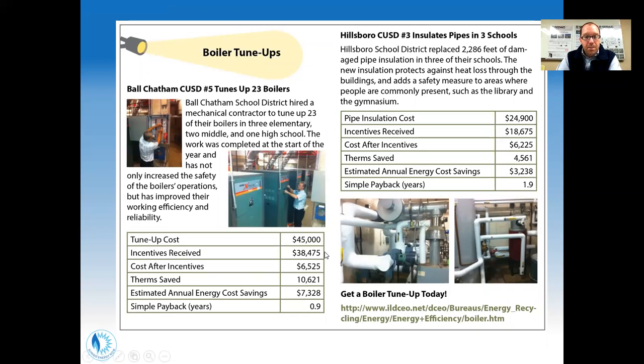The tune-up cost for these 23 boilers was $45,000. At the time, incentives only covered 85% of that cost—some now cover 100%. But they saved 10,000 therms throughout the year, every year, which amounts to $7,000 a year in savings. So it had less than a year payback in this case, making it an excellent program to take advantage of.